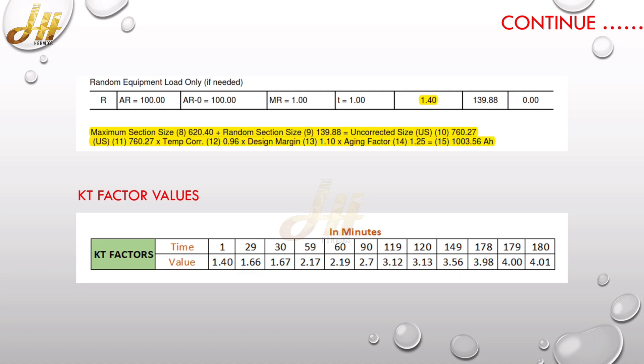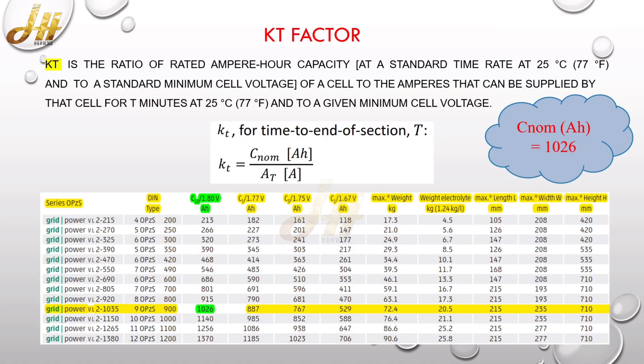Once we arrange the KT factor values, now we will go for what is KT factor and how it can be derived. So what is KT factor? KT is the ratio of the rated ampere-hour capacity of the battery, which is recommended by the manufacturer, with the ampere that can be supplied by the battery.